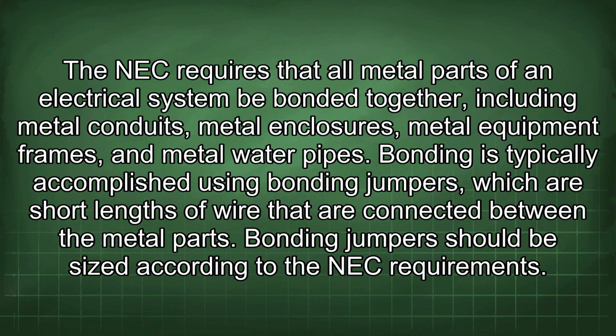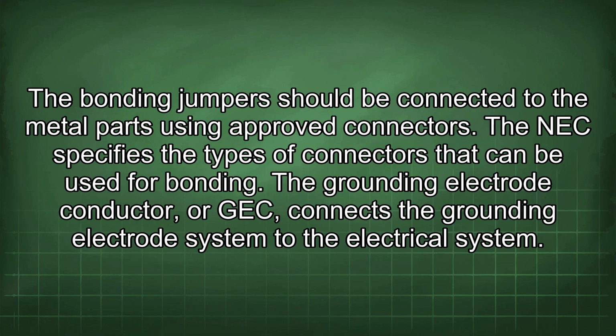Bonding is typically accomplished using bonding jumpers, which are short lengths of wire that are connected between the metal parts. Bonding jumpers should be sized according to the NEC requirements. The bonding jumpers should be connected to the metal parts using approved connectors. The NEC specifies the types of connectors that can be used for bonding.